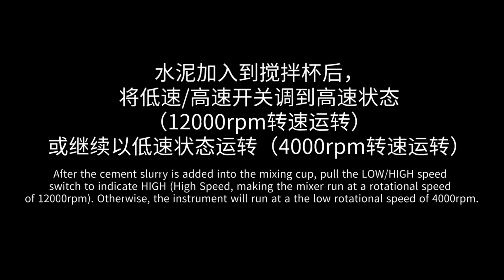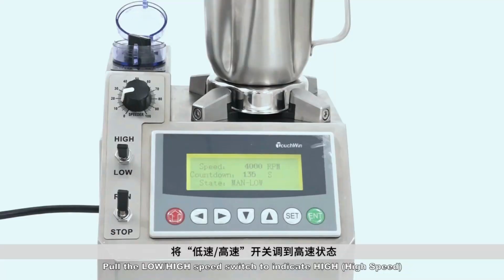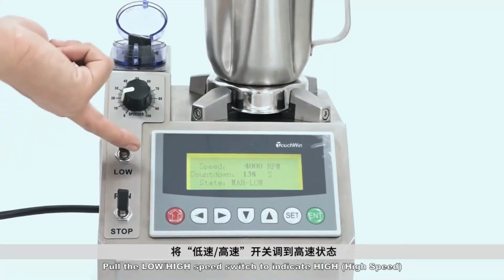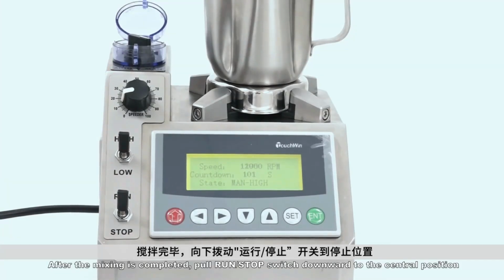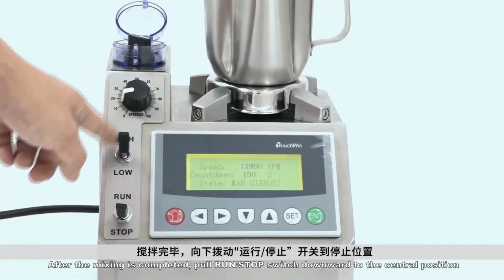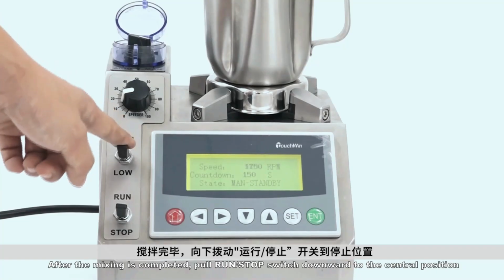After the cement slurry is added into the mixing cup, pull the low or high speed switch to indicate high speed, making the mixer run at a rotational speed of 12,000 RPM. Otherwise, the instrument will run at a low rotational speed of 4,000 RPM. Pull the low or high speed switch to indicate high speed. After the mixing is completed, pull the run or stop switch downward to the central position.